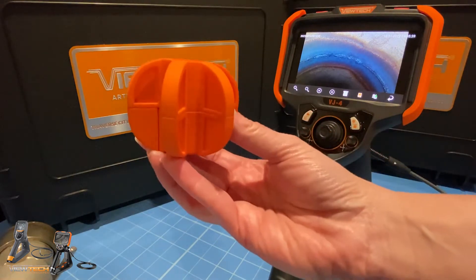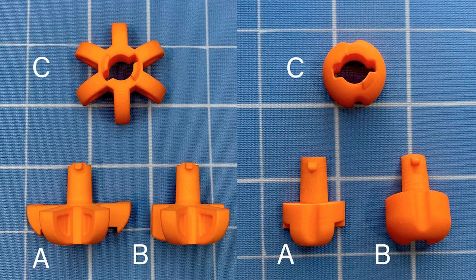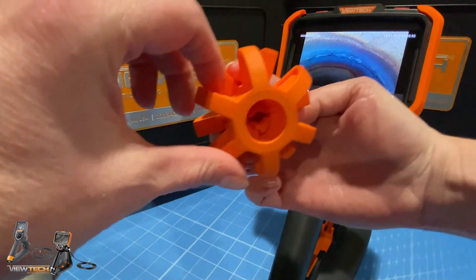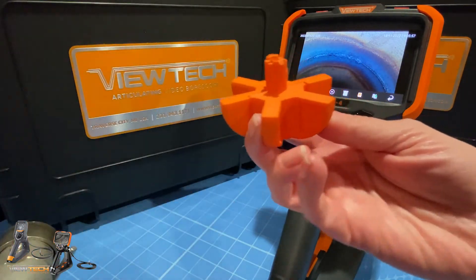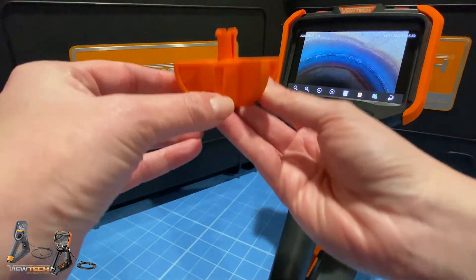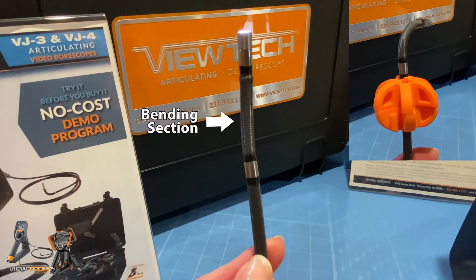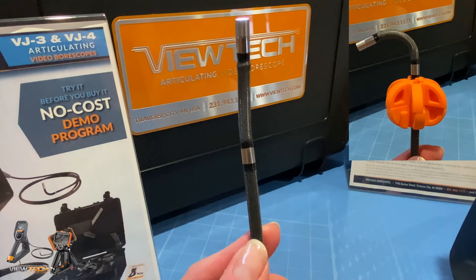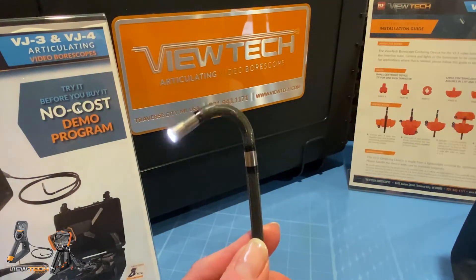ViewTech boroscope centering devices are made from a lightweight material and consist of three parts, which we will refer to as parts A, B, and C. It can require several attempts to gently align the notches and interlocking pieces when assembling and disassembling the centering device behind the bending section of the video boroscope. Install the centering device below the bending section — placing it over the bending section would prohibit articulation and could cause damage to the insertion tube.